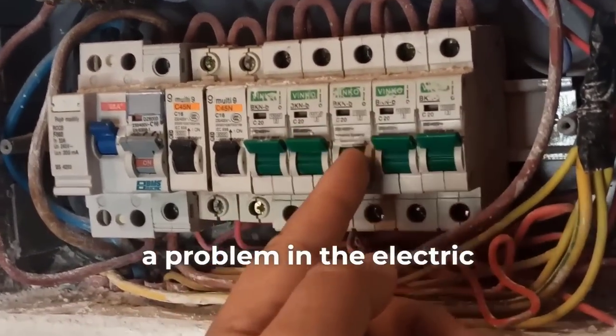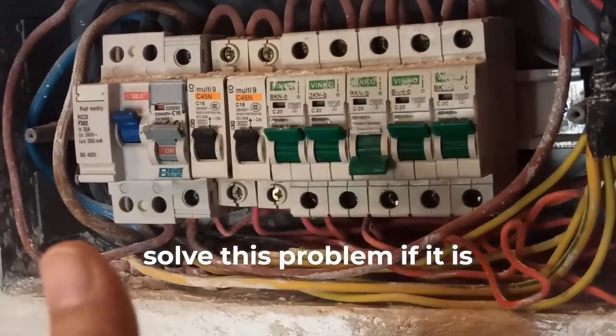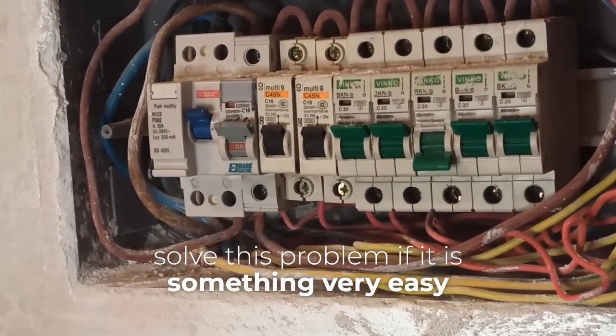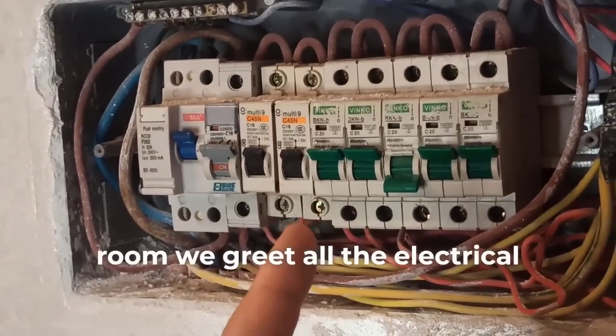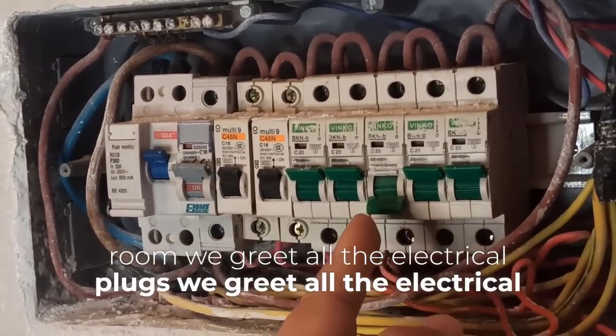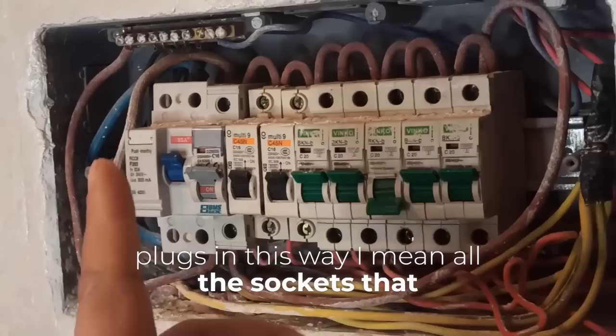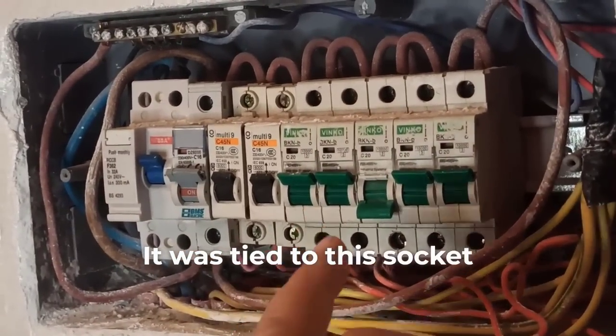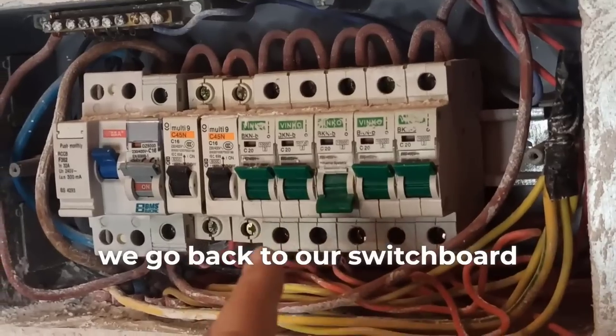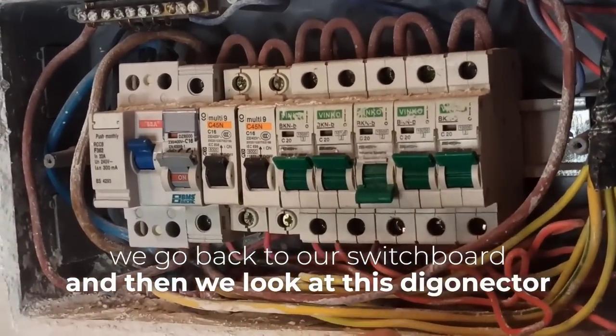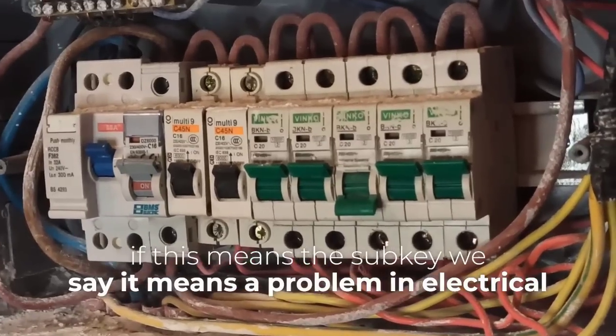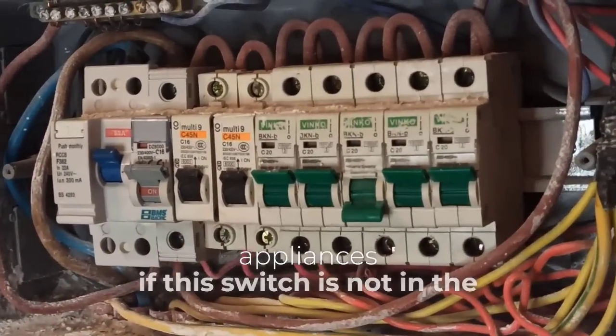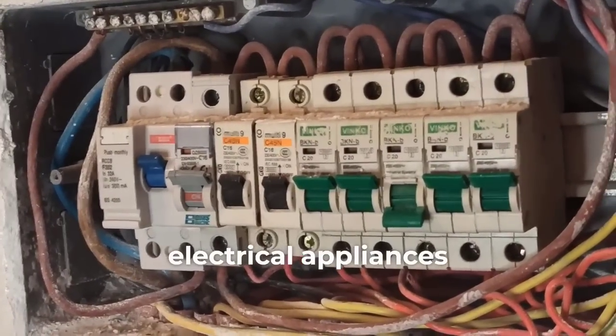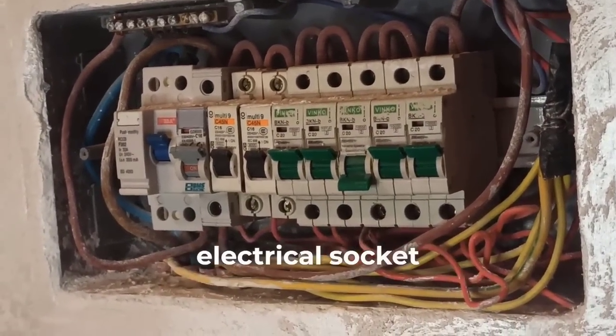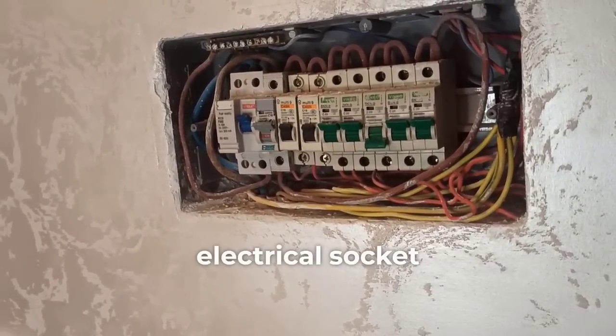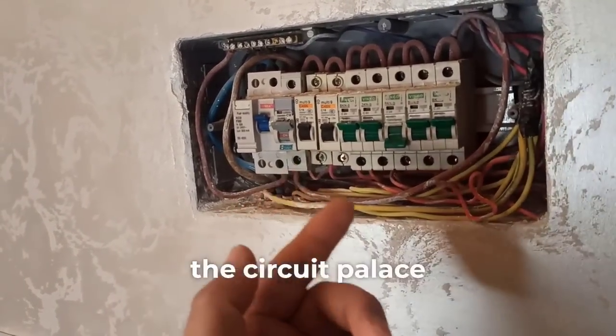If we have a problem in the electrical socket circuit in this room, how can we solve this problem if it is something very easy? The first thing, we go to this room and unplug all the electrical appliances from all the sockets tied to this circuit. If we unplug all these sockets, we go back to our switchboard and look at this breaker. If the breaker holds, we say the problem is in the electrical appliances. If the breaker still trips without the appliances, we say the problem is in the electrical socket. So this is how to determine the circuit location.